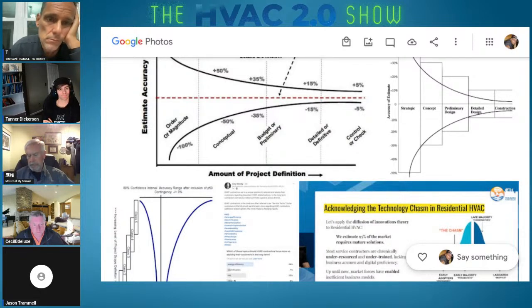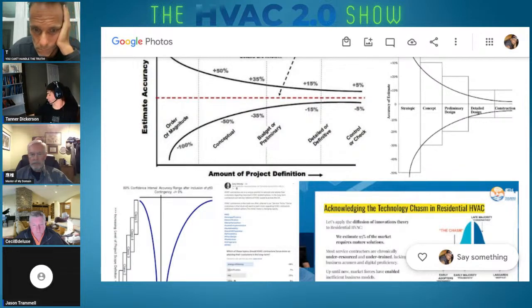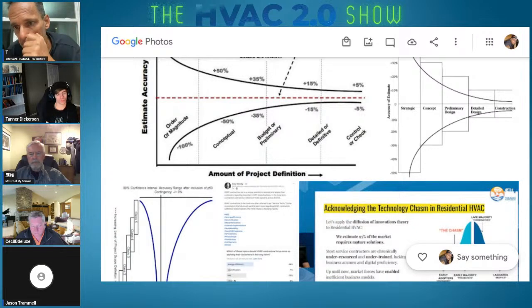Right. And you'll see that in older houses that have old gravity registers that are huge, with 12-inch supply ducts. Like the register's 8 by 20 or something. You can push 3 tons out of that one register, so it's hard to balance stuff like that. But at that point, if they're going to go with good equipment, they need to replace the ductwork and the distribution. Yeah. So.